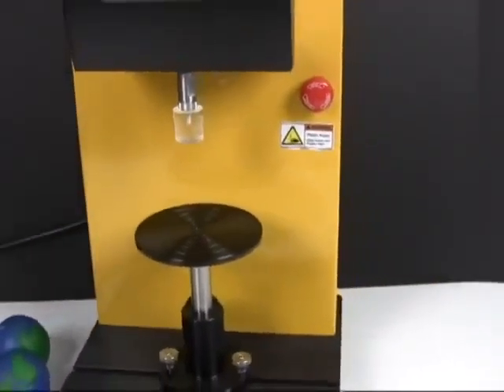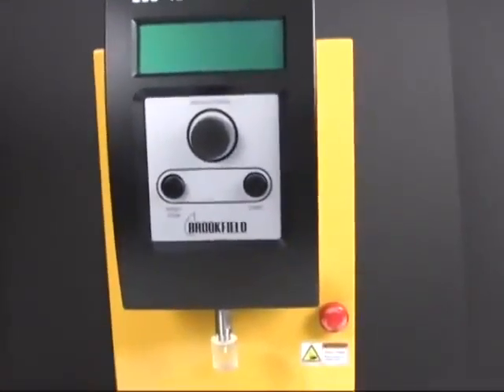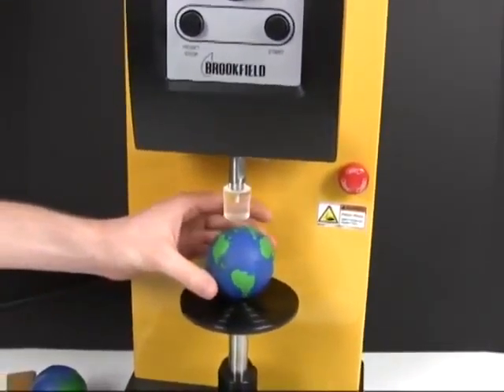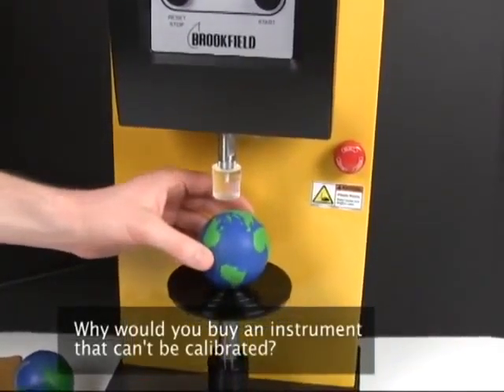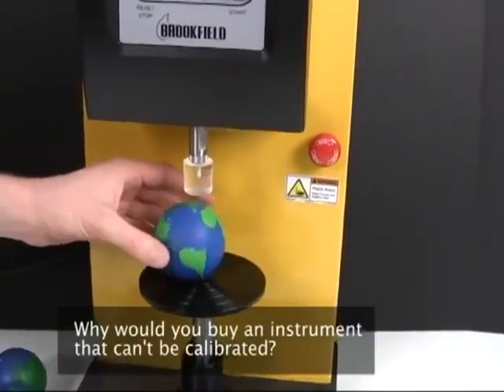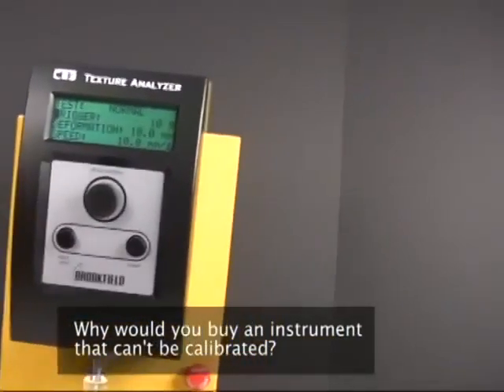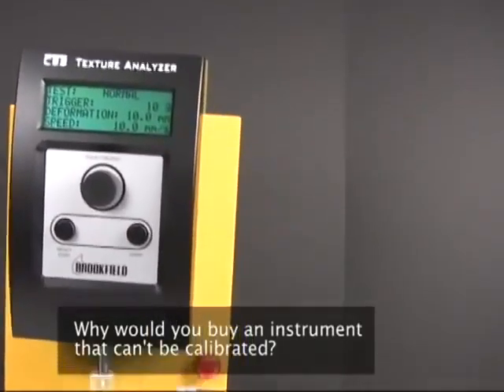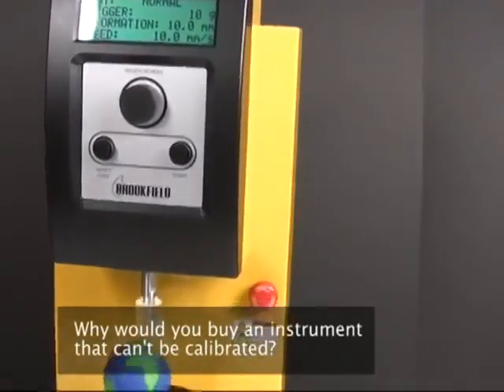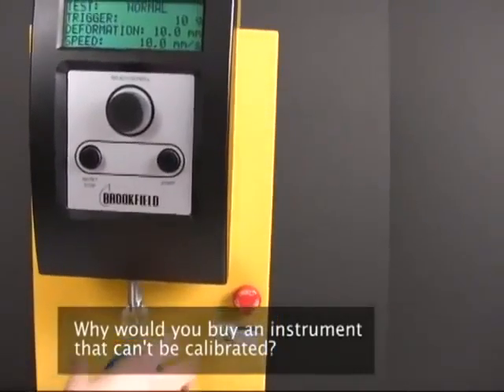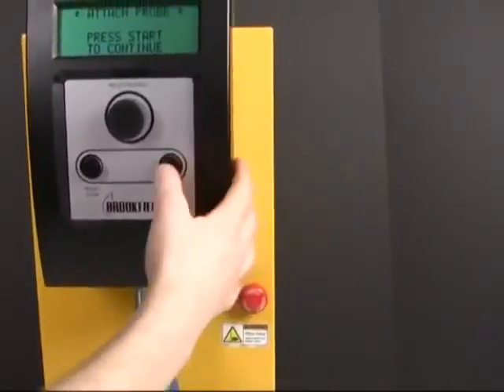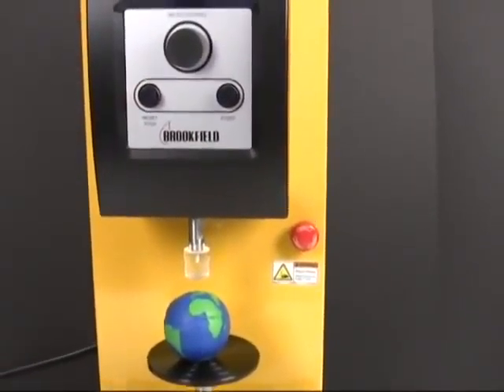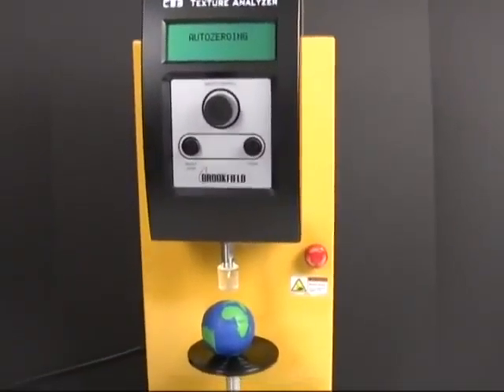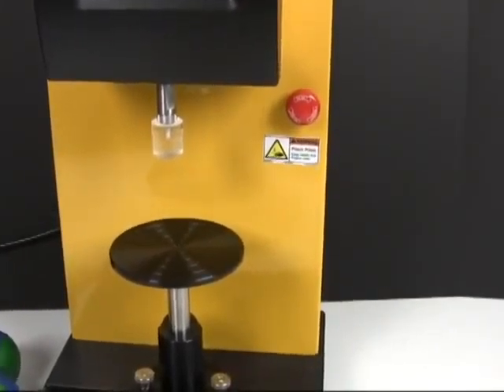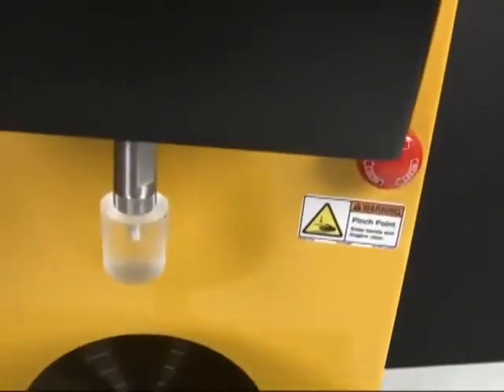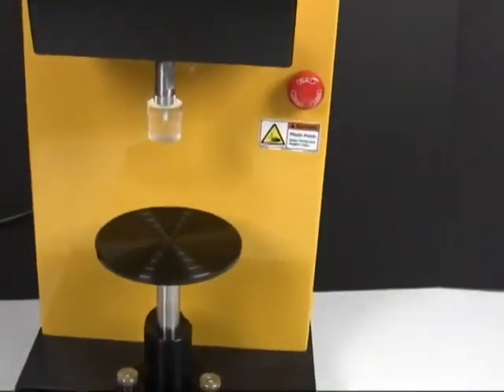In terms of setting up a test, we found out that you just can't calibrate the instrument at all. If you did buy the calibration hooks and you did have the weights on hand, you could go ahead and test and see how far it's off. But in the case that it is off, you're going to need to send it back to Brookfield to get calibrated. Now, ASTM E4 requires calibration when instruments are moved. And this lack of calibration is a big issue in a lot of industries that need FDA approval, such as any medical device, food, gel, or cosmetic companies.